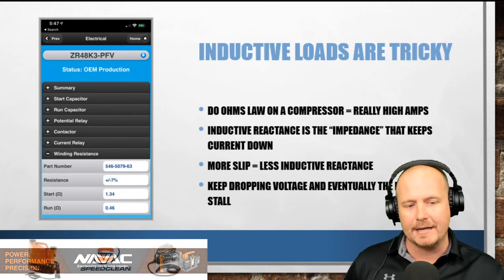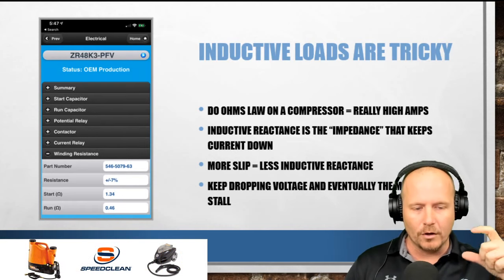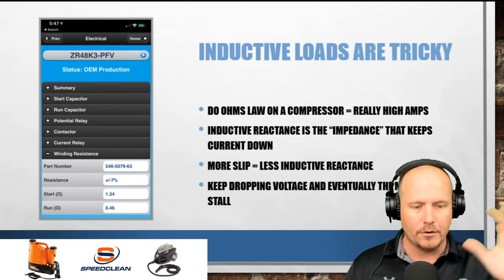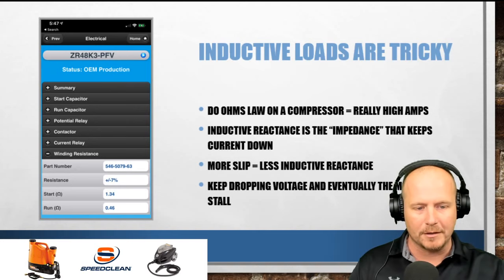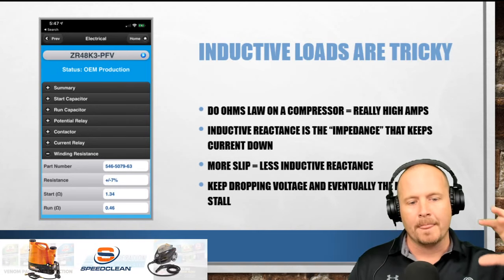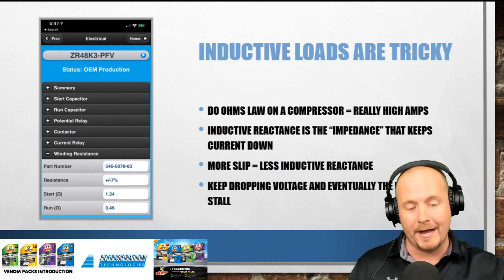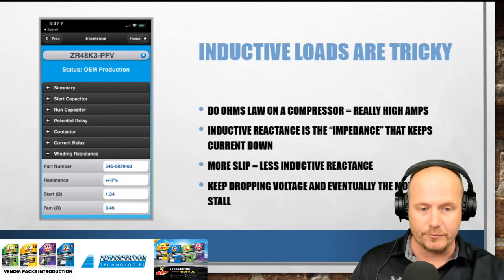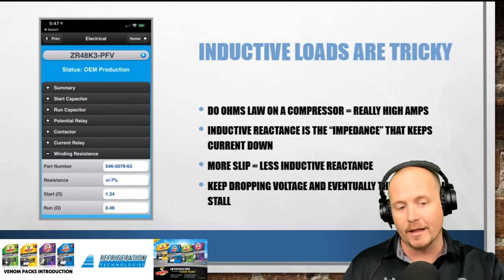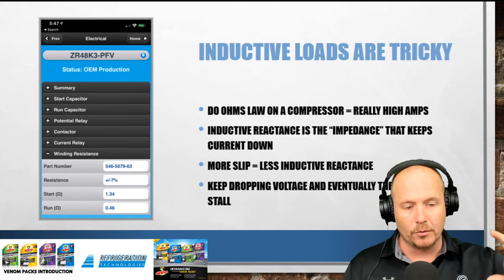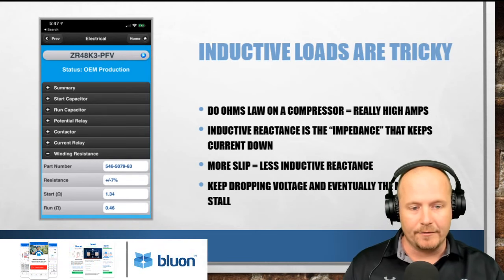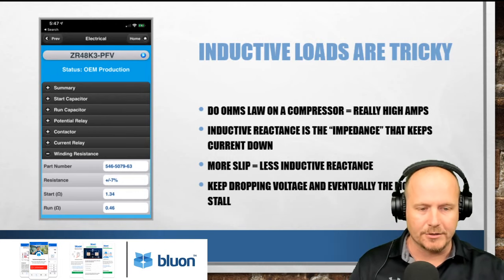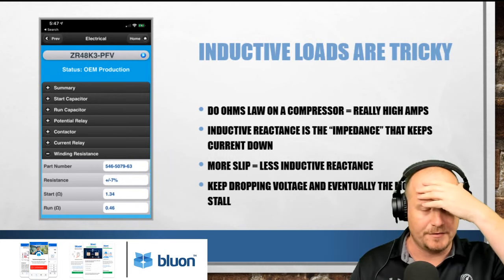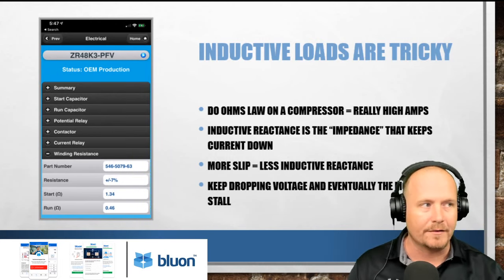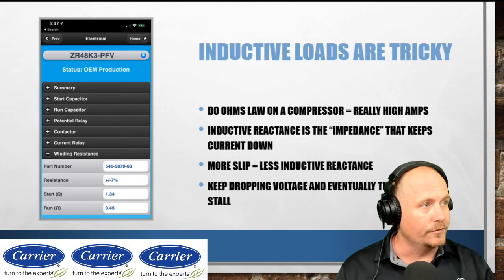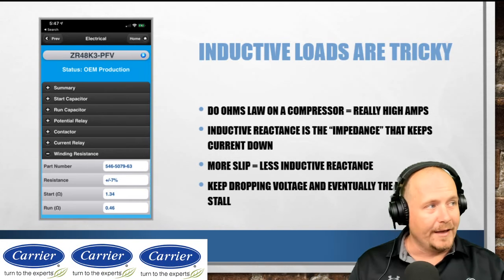Now, I was trying to find it, but certain manufacturers will also give charts to show on a 208/230 appliance, like a condenser, how it will produce less overall capacity when you run it on 208 than you do on 240. And the amperage will actually be slightly lower. So you'll have lower capacity, and you'll also have lower current. Again, on some of the charts that I've looked at, and I looked for 15 minutes, I couldn't find one, so I just let it be. But I've definitely seen that in the past. So if anybody wants to find that.